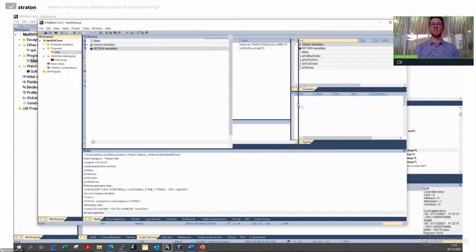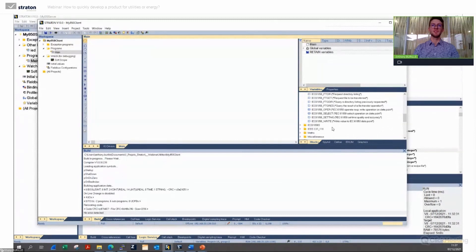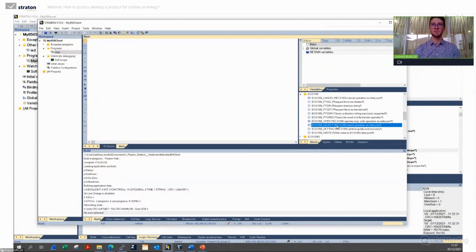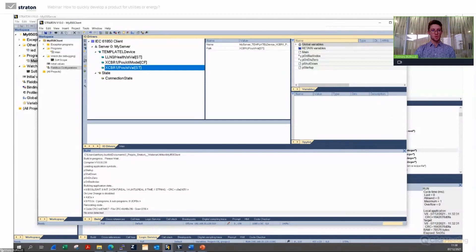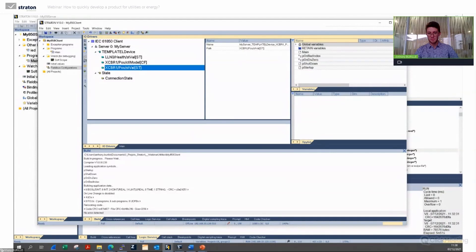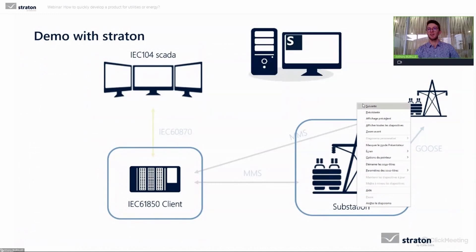Then I can create programs — I insert a new program, and I have the list of blocks available in the tree for everything linked to IEC 61850 — for example to write a value, make an operate on the circuit breaker position, select before operate, cancel the operation. Everything is available on the client side. We have videos on YouTube showing far more advanced configurations. So we see it already works — we created the basic SCL file, configured our substation, downloaded it to a Raspberry Pi transforming it into an 61850 substation with a blinking circuit breaker, and created the 61850 client.